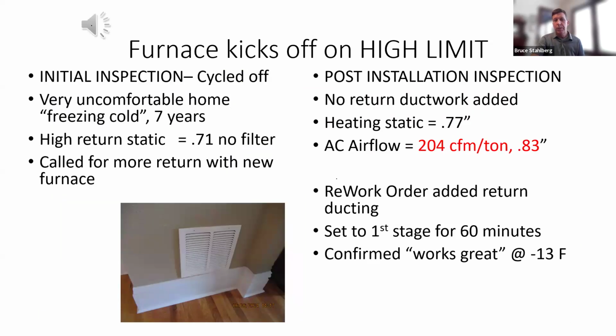Here's another example. My initial inspection on a new furnace. Actually, no, this was before anyone got out there. It was kicking off on high limit, meaning that it would turn off after a few minutes. She said they had lived there in a freezing cold home for 7 years. She told me sometimes they wear their winter coats in their home. We had high return static pressure. That was 0.71, with no filter in it, so that was all the ductwork. I called out for more return with the new furnace. I went out to do the inspection. They put in a new furnace, but somehow there was no more return ductwork added. I wasn't quite sure how that happened on our work order.